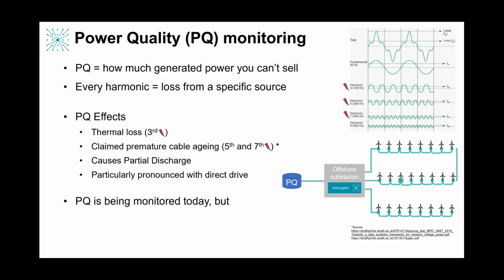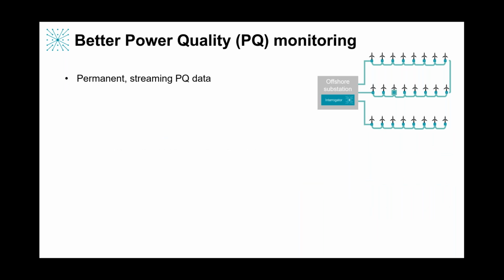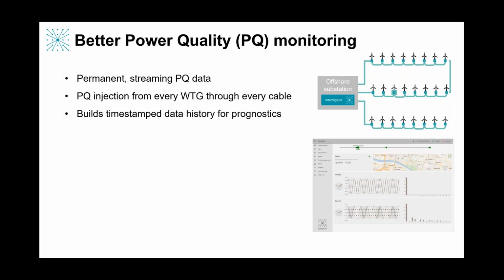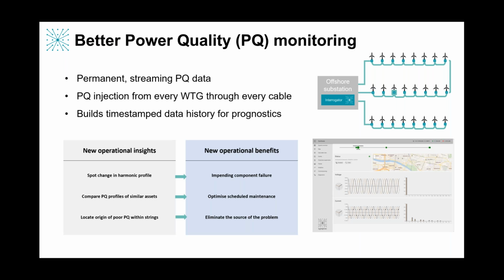So you'd think everyone monitors it, and they do today, but power quality is only monitored from time to time. It's not permanent, and it's only monitored at the output of an entire wind farm. So you get a net score of the effect of bad or good injections of power quality from every single wind turbine. That's good for grid compliance, but it doesn't tell you the origin of a problem or any particular turbine that's misbehaving. So the goal here is to say, let's enable permanent and streaming power quality data. Let's read out the injection from every single wind turbine in the array, because we can, because we've got a very big sensor budget and long range, we can instrument that now. And then from this, you can get this timestamp data history built up for prognostics purposes.